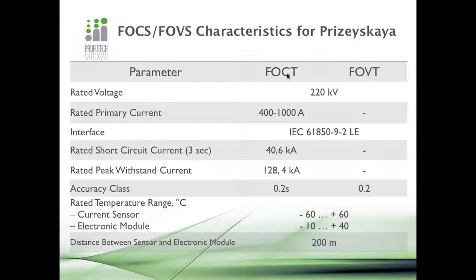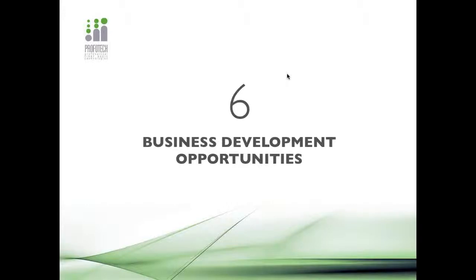As I said, you can see the range of primary rated current, which is from 400 to 1000 amps. The rated voltage is 220 kV, and the IEC 61850-9-2 interface is going to be used there. What's also special for this project, well, I don't think it's specific for India, but it's very, very important for Russia, is that the current sensor could work within the wide temperature range between -60 and +60 degrees Celsius.